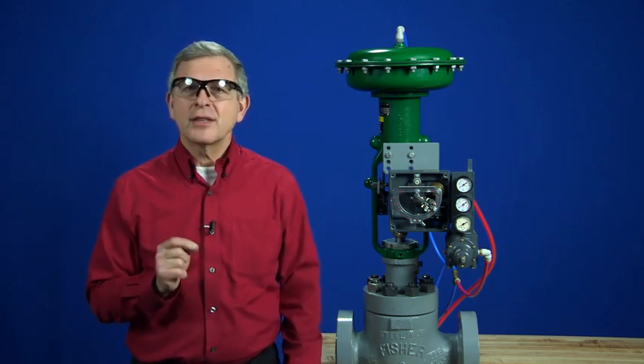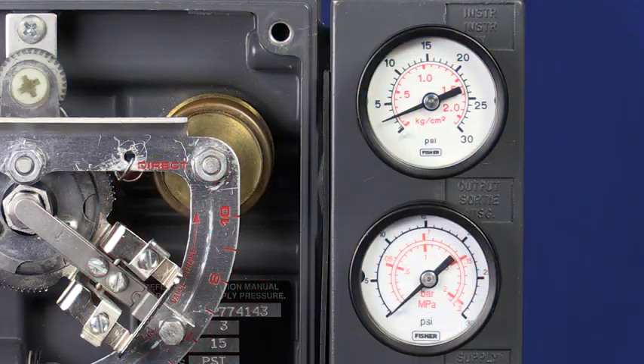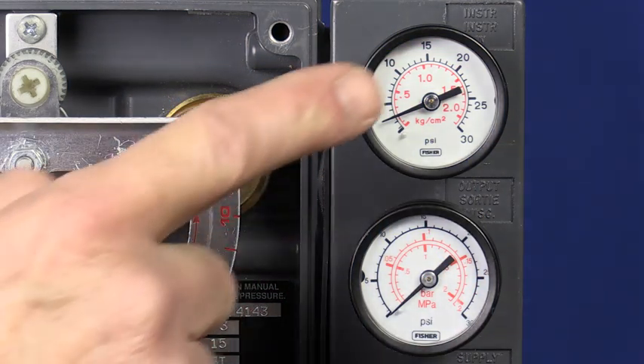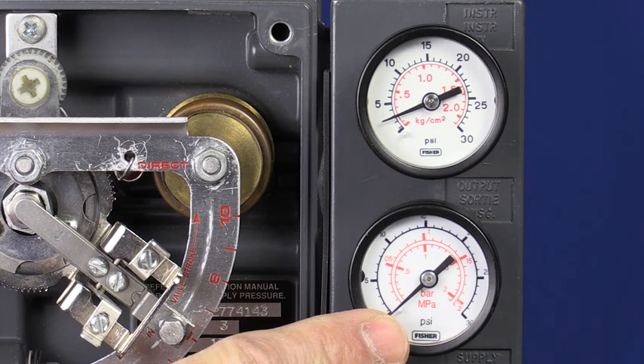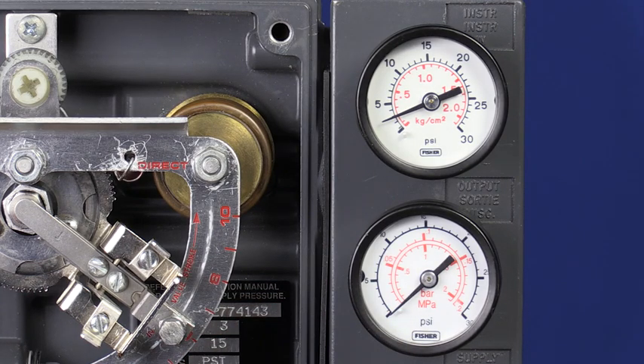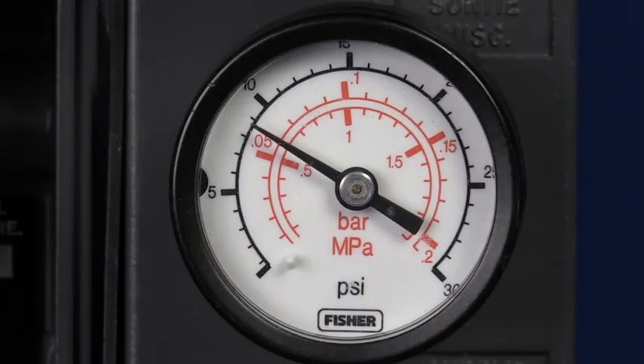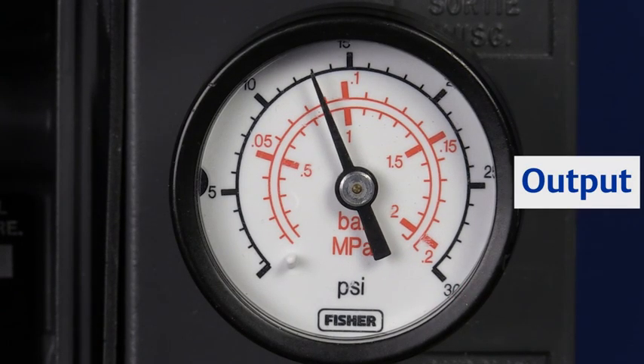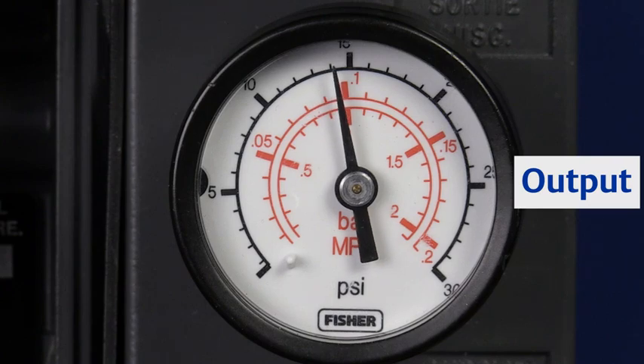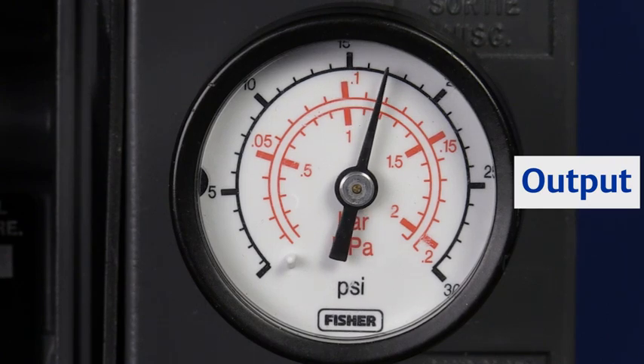Now, let's set the span. In step five, I'll increase the input pressure while watching the output pressure gauge. What I'm looking for here is saturation on the other end of the stroke. Saturation is identified when the output pressure rapidly changes and goes all the way to supply pressure. There it is.